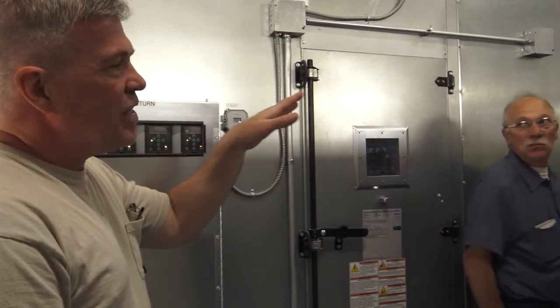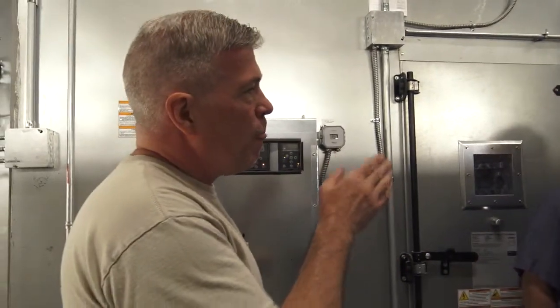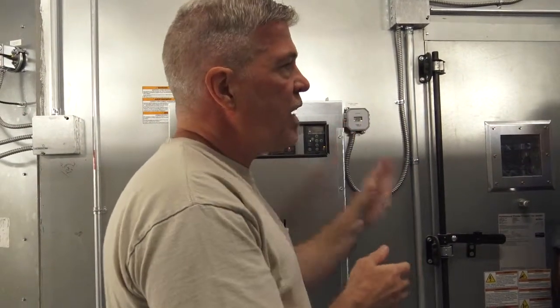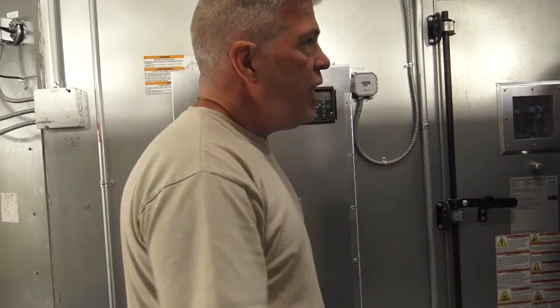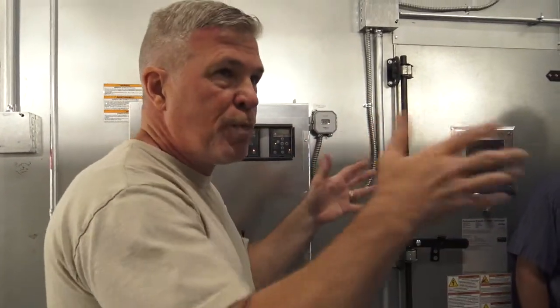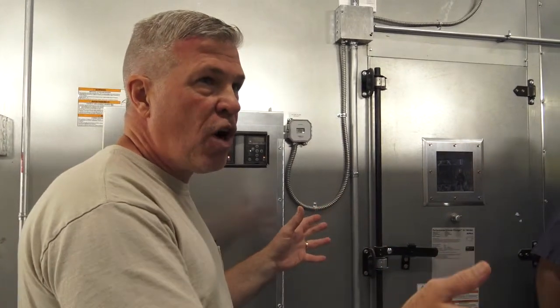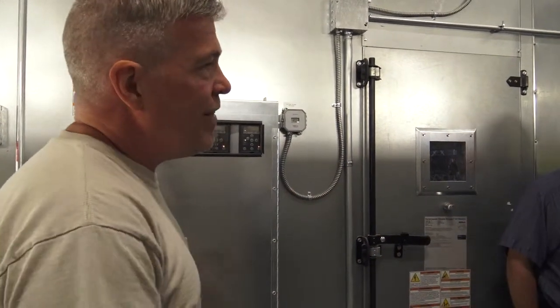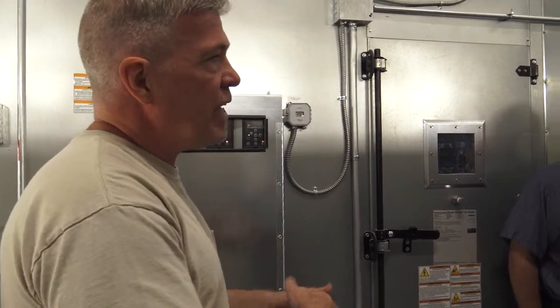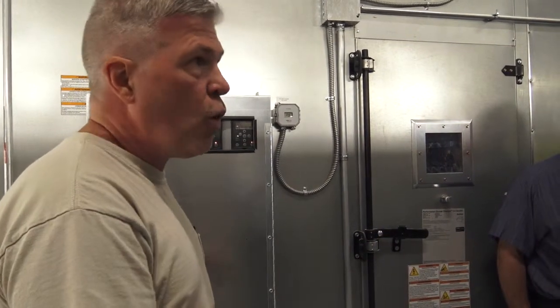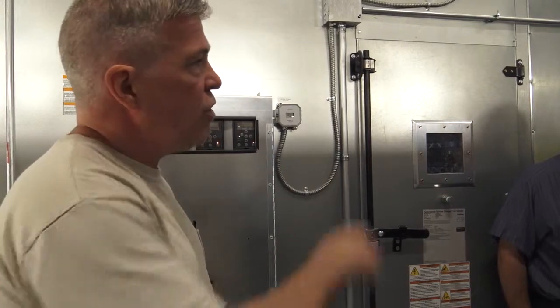But sometimes it's a little deceiving too, because one side is on the suction side, the other side's on the leaving side. So some filters will just produce a higher differential across them to start with, so that's kind of where you got to start with the number. Then based on either annual change or looking at the differential change, you can determine where you might want to change it.